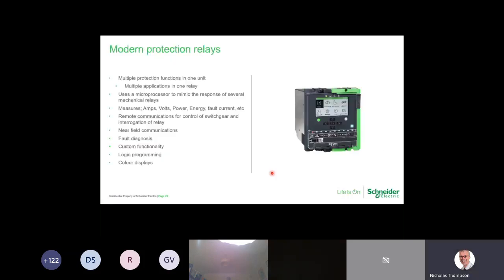So, touching more on what protection relays are. The picture there on the right is showing one of the more recent protection relays. We're introducing colour displays into there. We're introducing tricolour LEDs, so you don't just get an LED which pops on with a solid colour. You can actually have them doing all sorts of things, flashing different colours. So you could have green when it's healthy, you can have it amber when it's an alarm, and you can have it red when it's a problem.